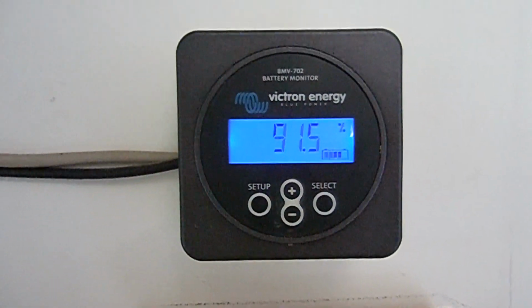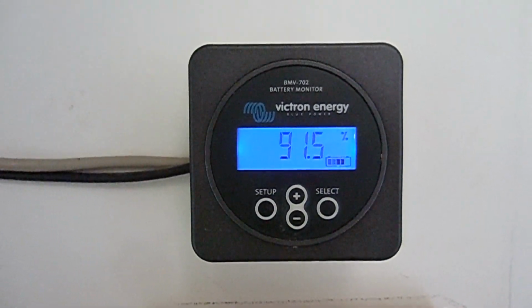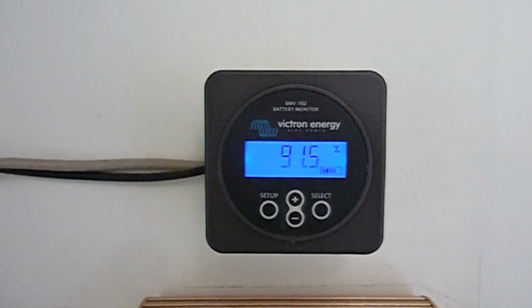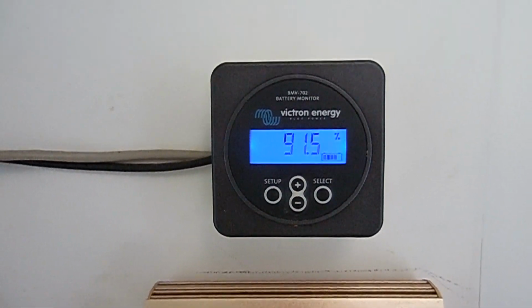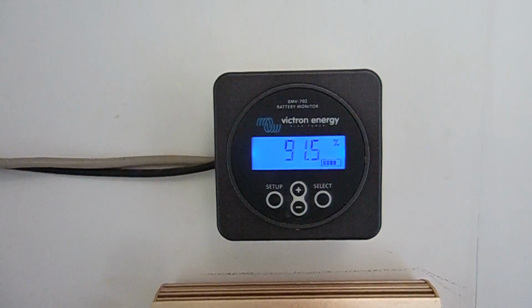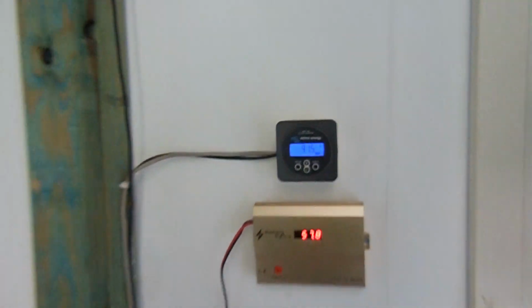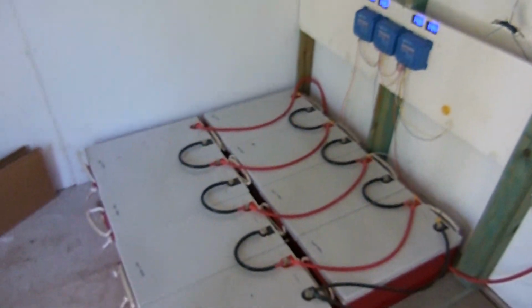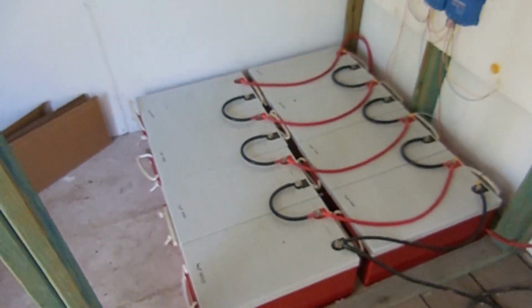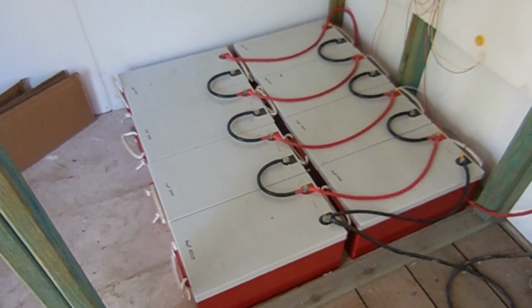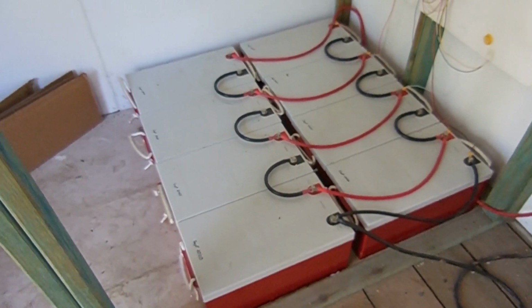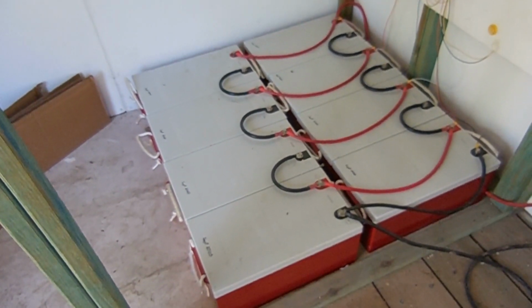That's our total percentage in the battery bank at the moment. I have an alarm set at 70%, so we never withdraw more than 30% of the available power out of the battery bank. You should never draw more than 50% out of a lead acid battery bank, so you can have maximum life, and we actually don't draw any more than 30%.